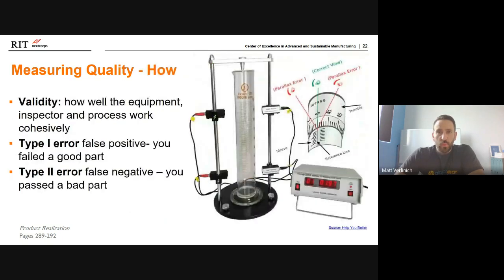So we'll talk about an example here of measuring quality and the validity. I love this example because validity refers specifically to how well the equipment and the inspector work coherently. You can have the best instrument in the world, but if your inspector isn't following a reliable, repeatable procedure, you can still get error. Graduated cylinders are an incredibly accurate way of measuring volume of liquids. However, if you remember from your high school chemistry class, you have to measure at the bottom of the meniscus, and then you have to look at eye level with it. If you look either down at it or up at the line, you will get an error in that. And so when you have many people trying to read and do this many thousands of times, those errors can compound and result in quality issues.